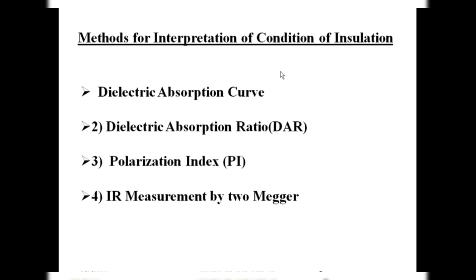The insulation condition is measured by the megger — an instrument that gives us the present value of the insulation of windings of the given electrical equipment. After measurement, there are four methods to interpret the condition of insulation: first, the dielectric absorption curve; second, the dielectric absorption ratio (DAR); third, the polarization index (PI); and fourth, IR measurement by two meggers.